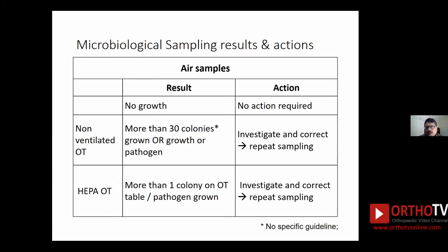For air samples, the ideal result is again no growth. In non-ventilated OTs without a HEPA filter system, not more than 30 colonies should grow on the plate — this is generally followed across most OTs, though there are no specific guidelines for non-ventilated theaters. No pathogen should grow — such as a gram negative, fungus, or Staphylococcus. For a HEPA filter laminar flow theater, the number of colonies allowed on the OT table is not more than one — zero or one — and anything more than that requires investigation of the system.